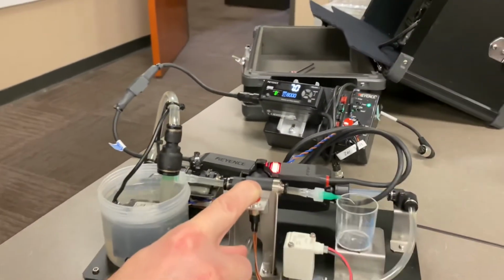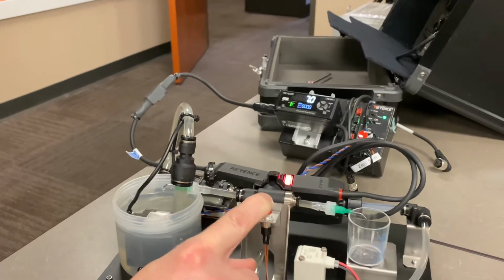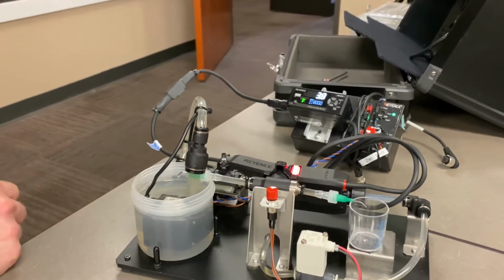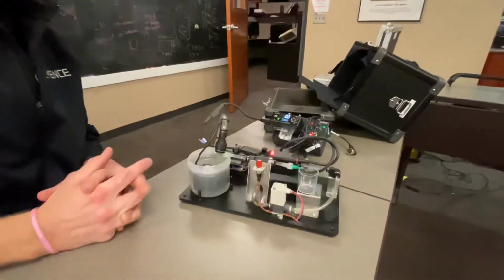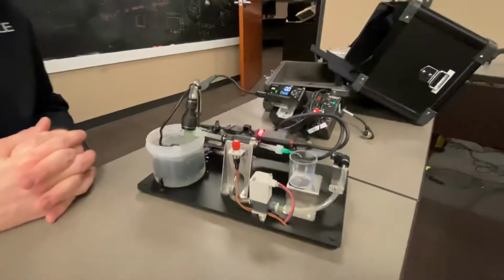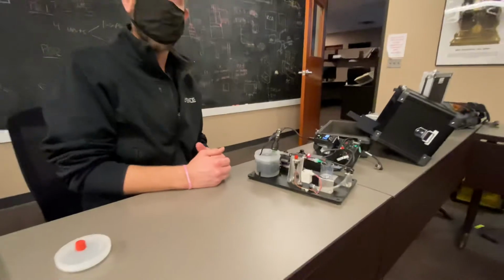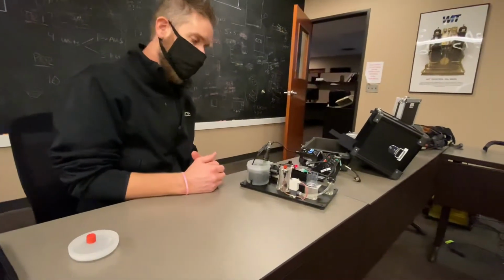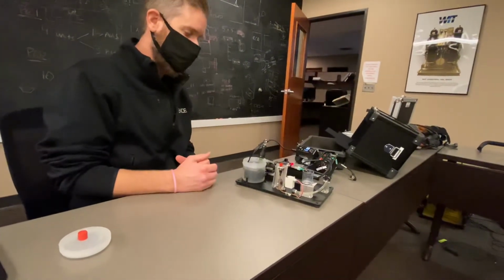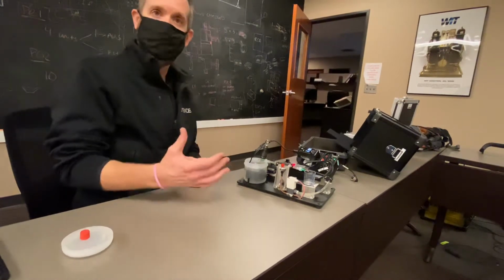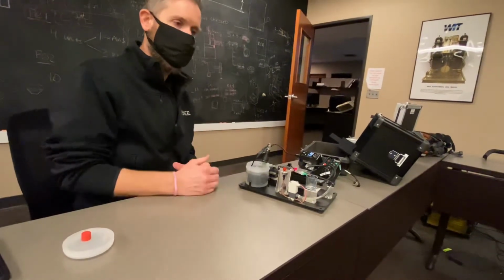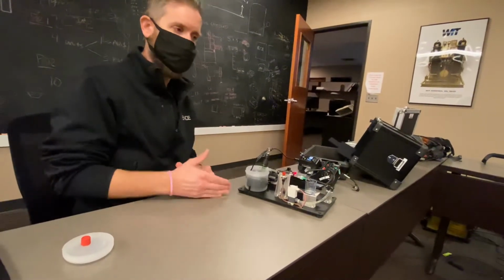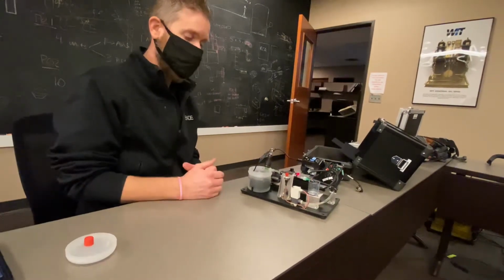Wow. Accuracy on these are plus or minus 0.1% of the full range of the sensor. And the repeatable accuracy, I think you're going to actually find you're well within that. So once you calibrate the unit to a known flow rate, or do a quick bucket test or something and calibrate the flow sensor, the repeatable accuracy of these things is spot on.